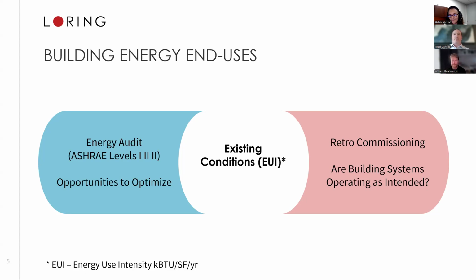It's important that when we're designing these systems, one of the new LEED requirements during commissioning is a current facilities operations and maintenance plan. It's both a training system and a guidebook for how to drive the building, for building engineers going forward. It really gets built in during design, especially when bringing on your commissioning agent or energy auditor, making it a deliverable they provide to the building during design, so it's built in and contractors know what training they're expected to provide, and the commissioning agent trains the building operators on it.